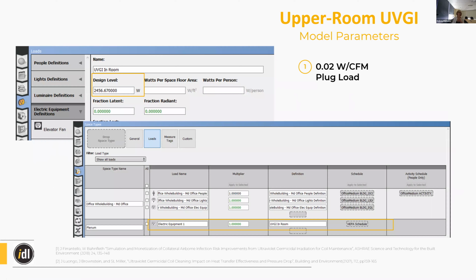As far as upper room UVGI, that was just a big plug load. We modeled it as the same type of lamp, but the difference with the in-room is that you just need that much more. So instead of two little lamps pointed at your coils or within your ultra reflective air handling unit, it takes a lot more lamps to disinfect an entire room, the air.